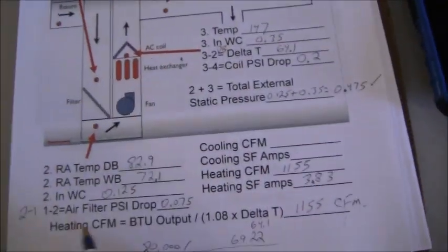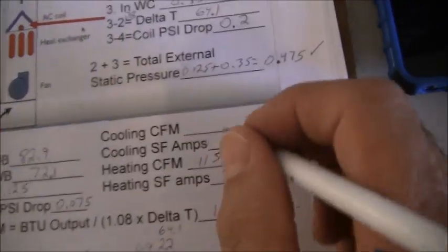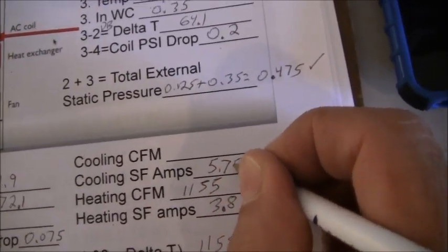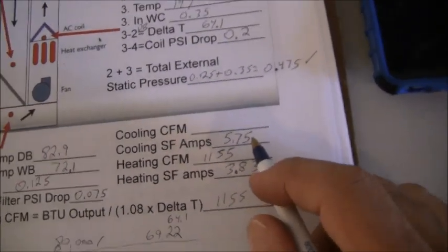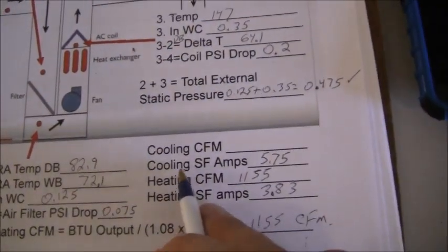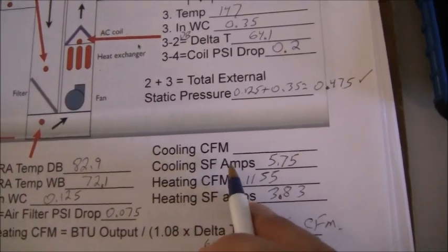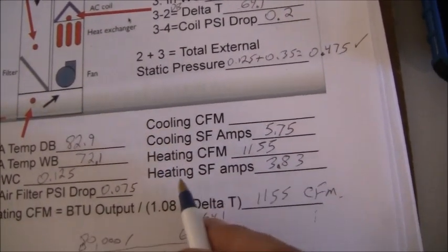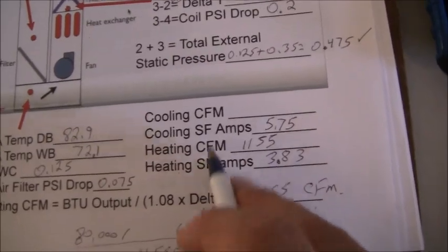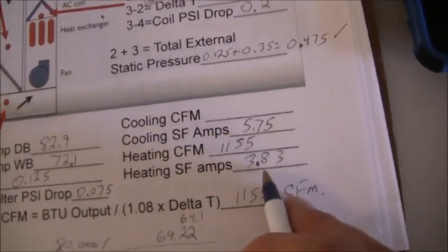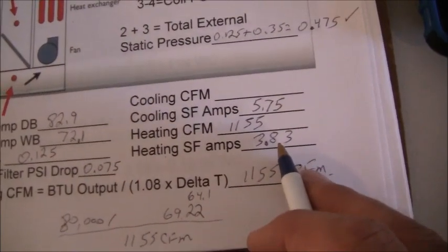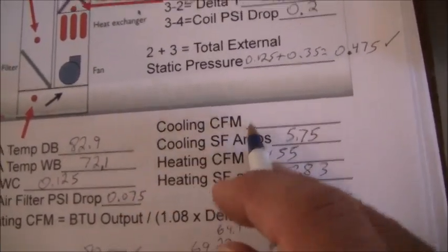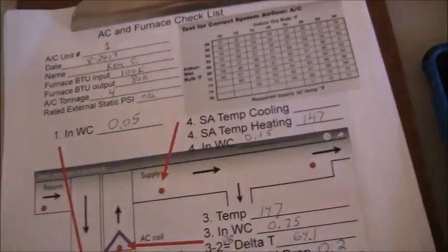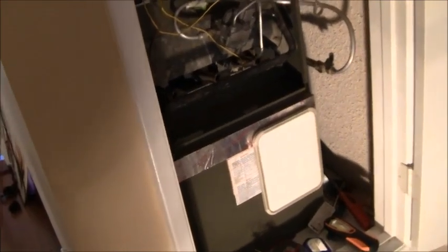Okay, so that is going to be supply fan amps, 5.75. By the way, it's not unusual for furnaces to have the cooling speed at a higher fan setting than the heating fan setting. This is a normal situation. I'm just documenting that and recording it and seeing exactly what it is. We'll try to figure out what the cooling CFM is once we fill in our data. Now that the unit has actually started, we need to give the compressor a few minutes, at least 10 minutes, if not 15 minutes.